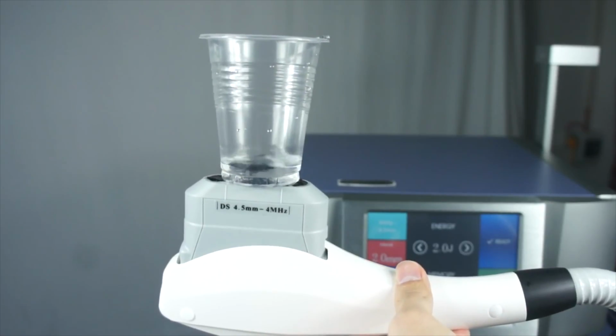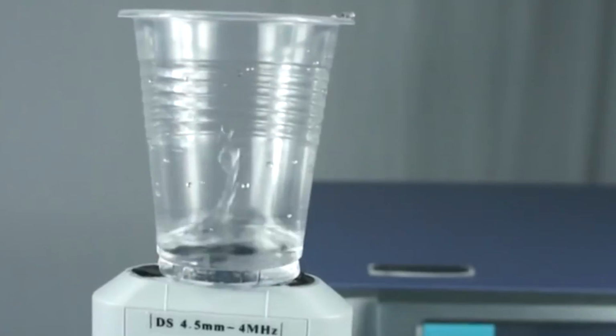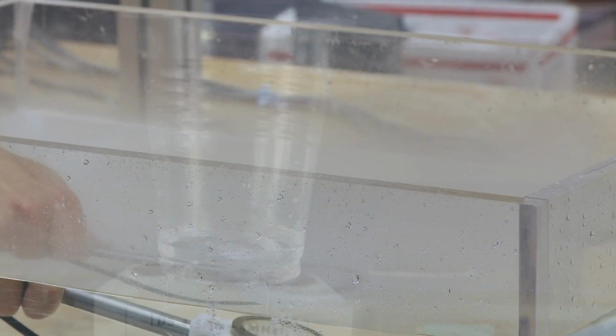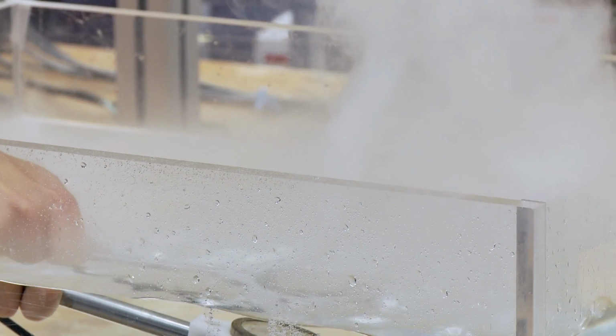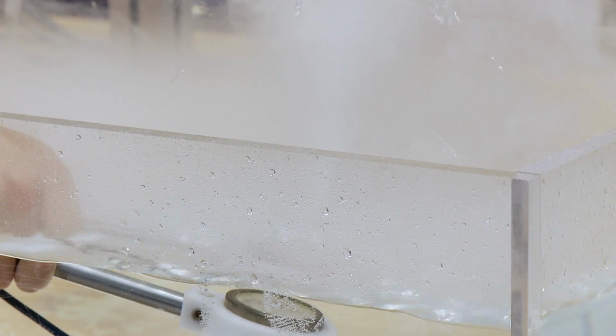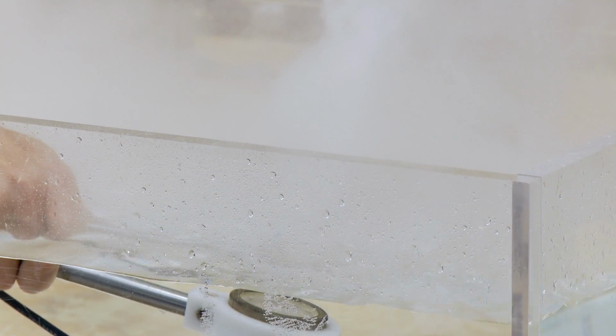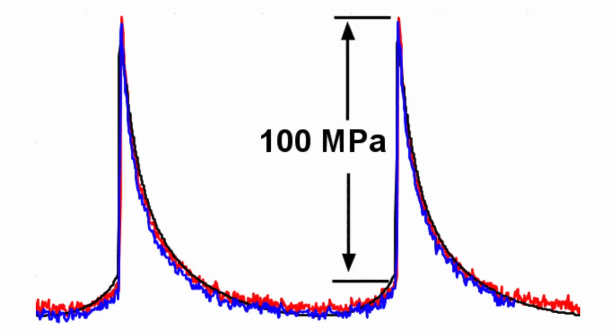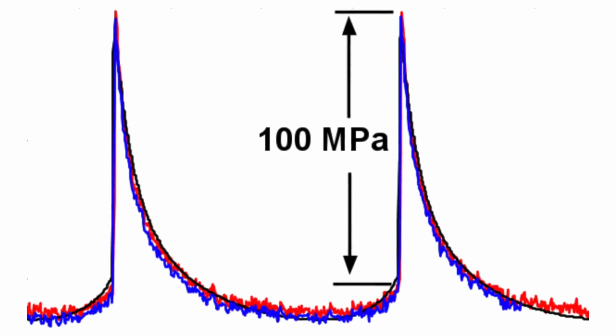In thermal HIFU, power levels for thermal ablation are continuous and relatively low level. Boiling histotripsy is a very different story. In boiling histotripsy, we are outputting very high power levels for a very short period of time. And so most of the traditional HIFU electronics and transducers that are used aren't capable of producing the type of pulses and the type of power levels that are needed for boiling histotripsy. One of the things that we've been working on is producing these instruments.